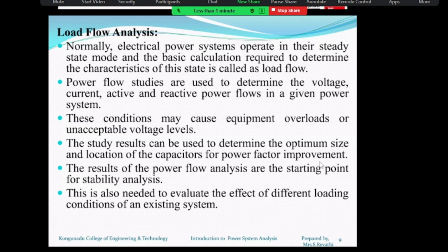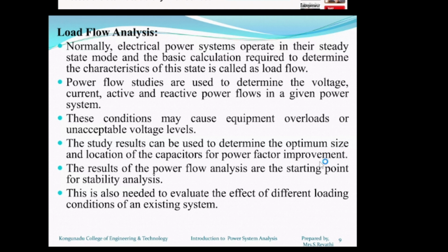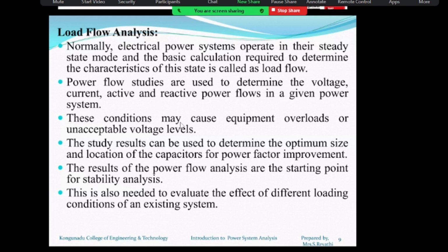The results of power flow analysis are a starting point for the stability analysis. These conditions may cause equipment overload and unacceptable voltages. The study results can be used to determine the optimum size and location of capacitors for power factor improvement. We do power system studies to determine the size and location of the capacitors or shunt devices, like where to place them on the transmission lines, for power factor improvement.